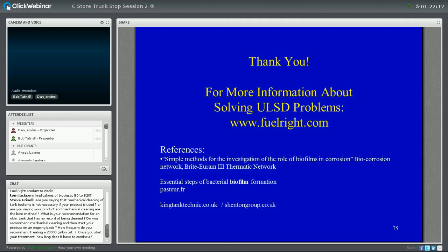Now, how long does it take for it to work? It takes minutes or hours for it to start to work. Depending on how much accumulated sludge you have, it could take weeks or even months to really break it down. It might take several treatments over a year or two to really clean up a badly fouled tank. That's why I say if you want quick action, send somebody in to shovel and scrape.